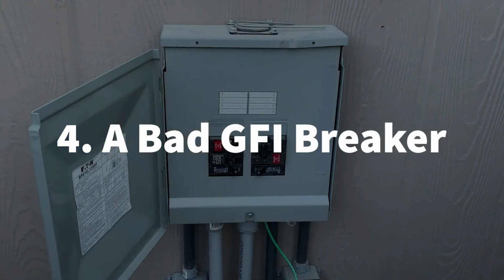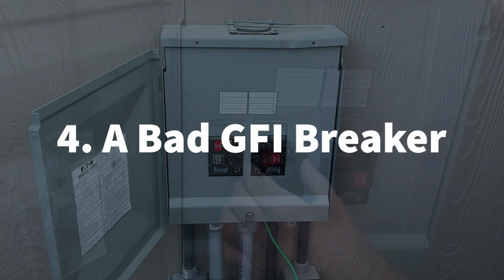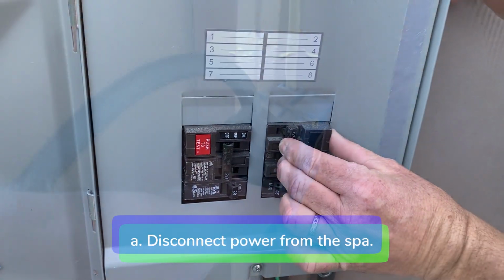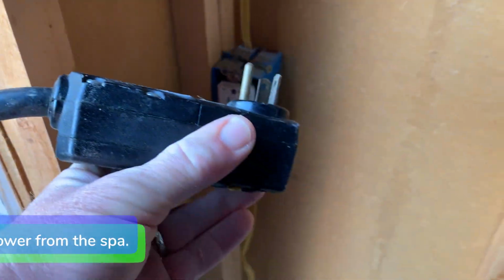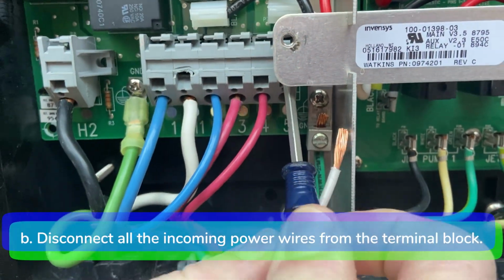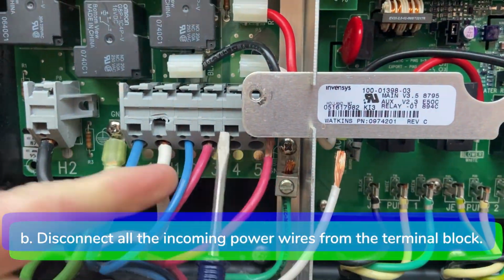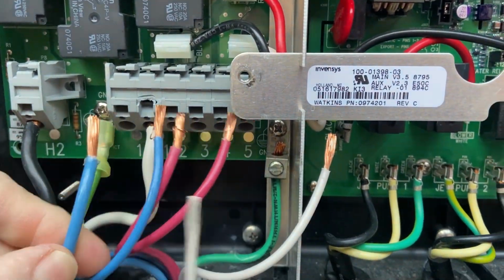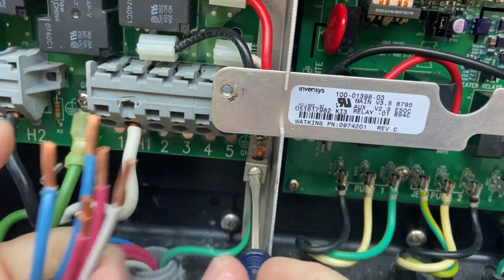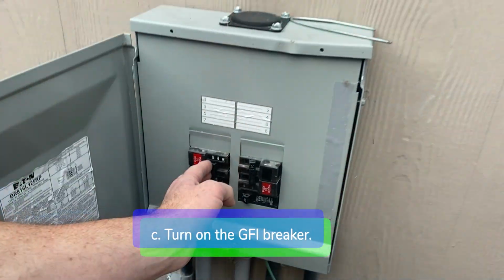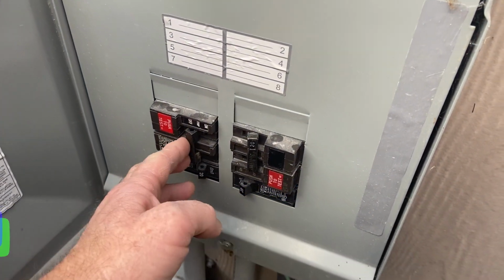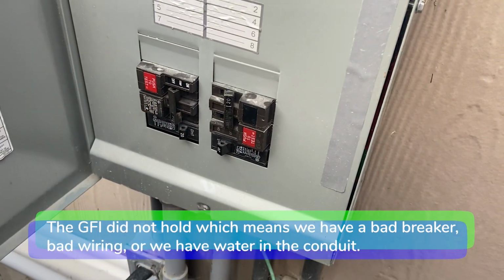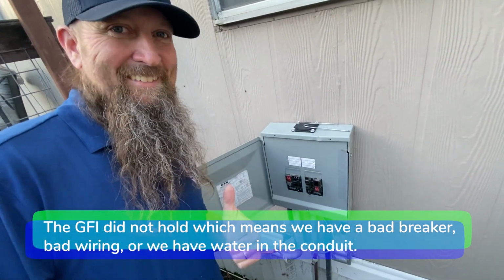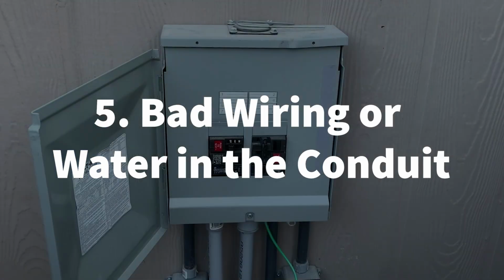4. A bad GFI breaker. To troubleshoot a bad GFI breaker, follow these steps. A. Disconnect power from the spa. B. Disconnect all the incoming power wires from the terminal block. C. Turn on the GFI breaker. The GFI did not hold, which means we have a bad breaker, bad wiring, or we have water in the conduit.